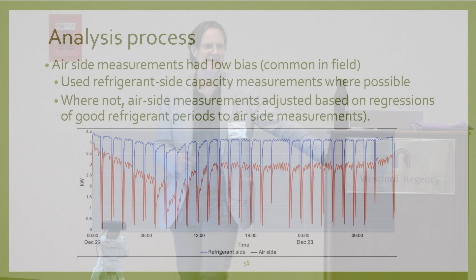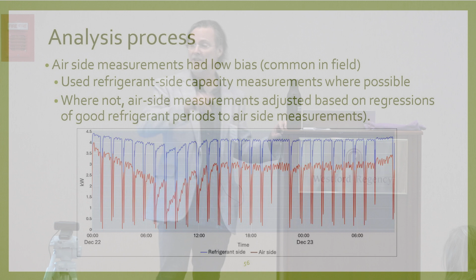So what they did is, well, we couldn't actually trust the refrigerant measurements all the time, because sometimes it's liquid or gas going through that pipe, and sometimes it's two-phase, and when it's two-phase, those measurements aren't good. But we know whether it's two-phase based on some of the other sensors, and so the team at UNL was able to say, we'll get a fit between the air side measurements and the refrigerant side measurements, and for all of those minutes that we don't have good refrigerant measurements, we'll use that curve fit to backfill what the proper capacity was. And I think they did a pretty good job of that.